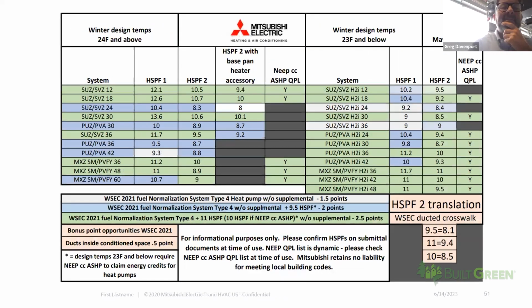This here is under the new Washington State Code. When you use that crosswalk translation document, you can actually see that we've got a lot of products that will meet the code and get everybody 1.5 points for fuel normalization, plus the 1 point for the high efficiency heat pump system, and if you can do ducts inside, another 0.5 point. So this is kind of the cheat sheet for HSPF 2 under our new code that's coming.